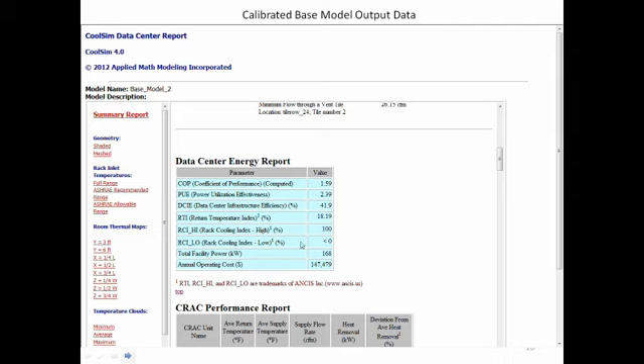So the summary report contains this, and there's a few things we can note about this right away. COP, Liz, 1.59. Pretty low, pretty low. Awful. Yes. PUE 2.3, which means that we're spending as much electricity powering the cooling systems as we are powering the IT equipment. Yeah, that's right. RTI, 18%.